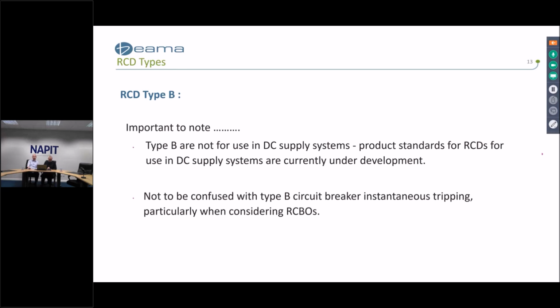And the second point to note is RCD Type B are not to be confused with Type B circuit breaker instantaneous tripping. It can be confusing, but there is a very different aspect to Type B instantaneous tripping, and it mustn't be confused, particularly when considering RCBOs.